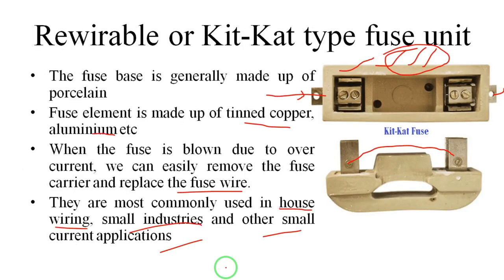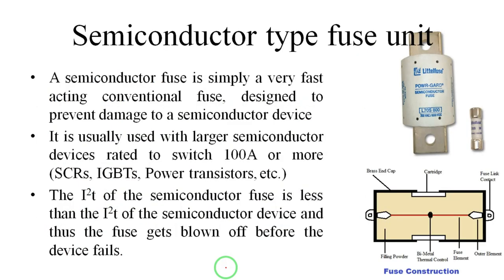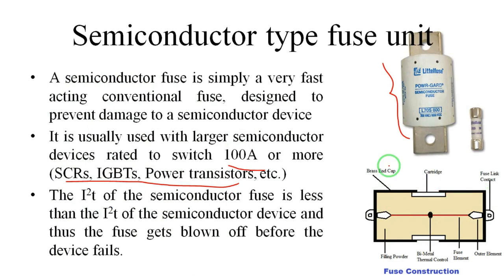The fourth type is the semiconductor type fuse. These fuses are used to protect semiconductor devices such as SCRs, IGBTs, and transistors. To protect these devices from high current, we use this semiconductor type fuse. The current capacity is 100 amperes. This fuse is similar to the HRC type fuse — it has a metal body, filling powder, a fuse element, and two caps.